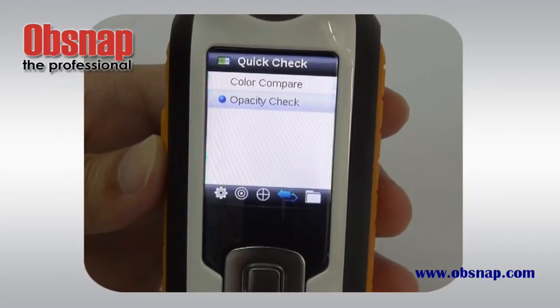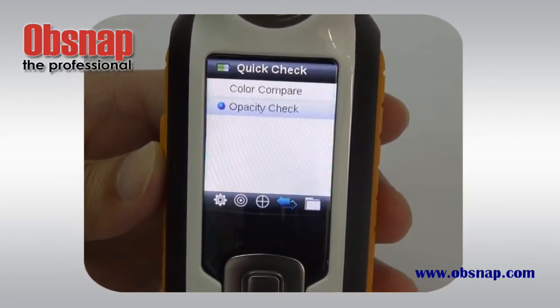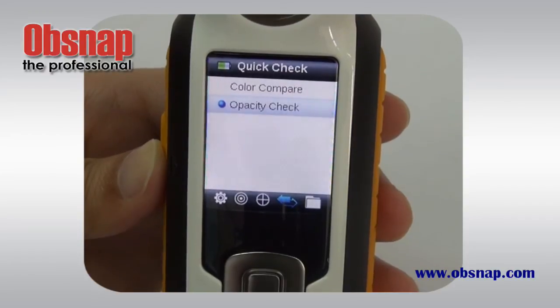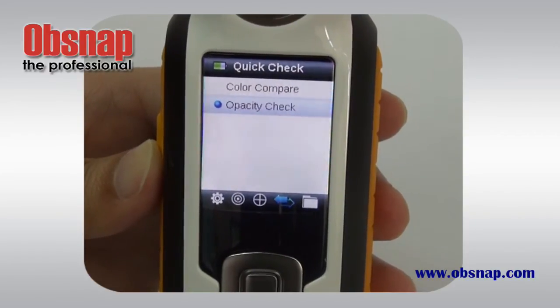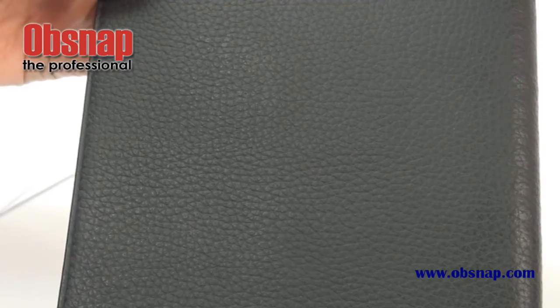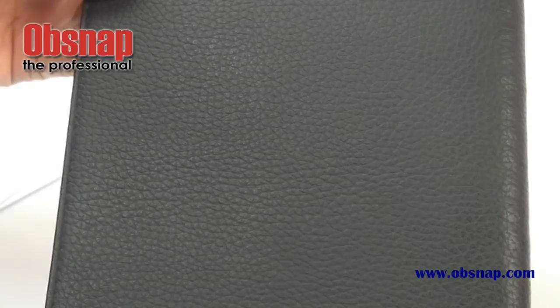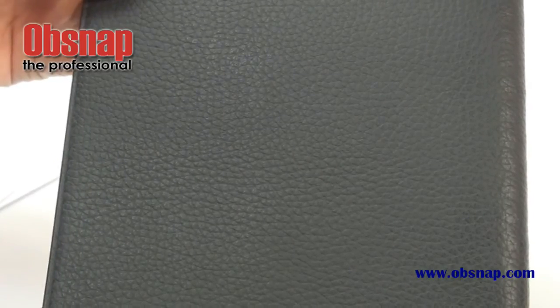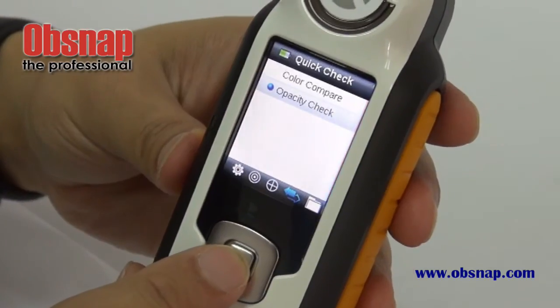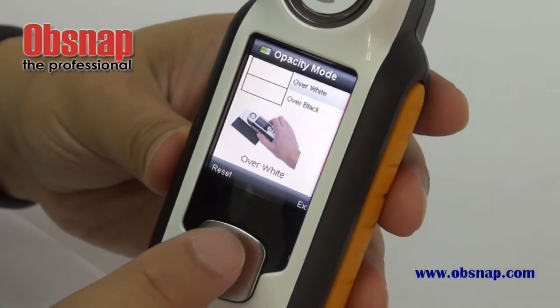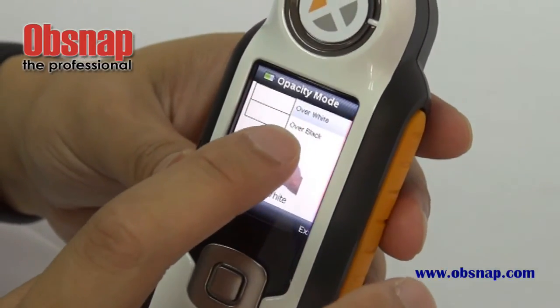Aside from doing color matching, this RM200QC is able to do opacity check. Opacity check is actually to measure a transparent product, something like this, which is somewhat transparent. When the transparency is high, the opacity is low. When the transparency is low, the opacity is high. To measure opacity, we need to have two background colors, which are black and white. When we select opacity check, the unit will ask us to measure over white and over black.